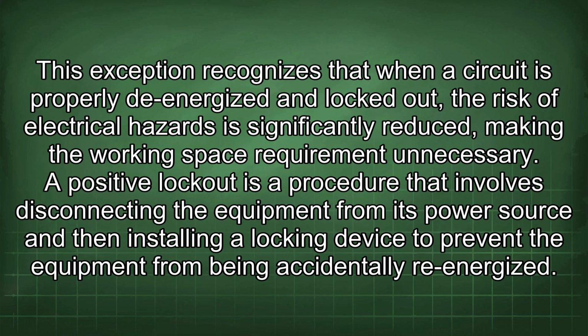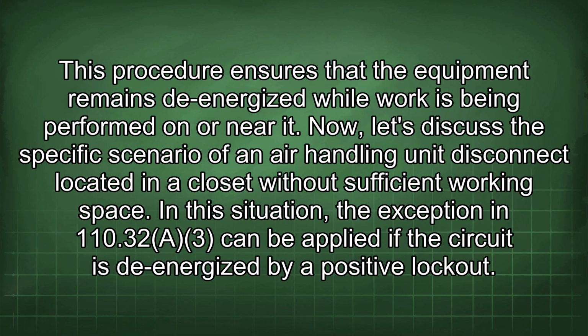This exception recognizes that when a circuit is properly de-energized and locked out, the risk of electrical hazards is significantly reduced, making the working space requirement unnecessary. A positive lockout is a procedure that involves disconnecting the equipment from its power source and then installing a locking device to prevent the equipment from being accidentally re-energized. This procedure ensures that the equipment remains de-energized while work is being performed on or near it.